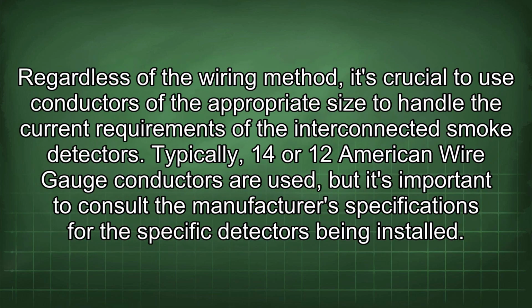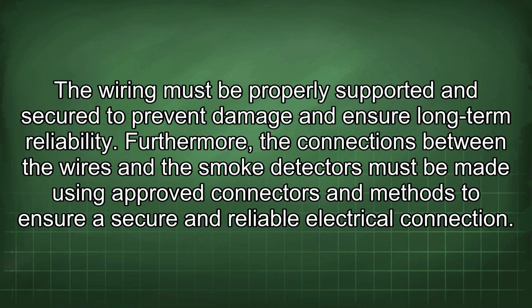Regardless of the wiring method, it's crucial to use conductors of the appropriate size to handle the current requirements of the interconnected smoke detectors. Typically, 14 or 12 American wire gauge conductors are used, but it's important to consult the manufacturer's specifications for the specific detectors being installed. The wiring must be properly supported and secured to prevent damage and ensure long-term reliability. Furthermore, the connections between the wires and the smoke detectors must be made using approved connectors and methods to ensure a secure and reliable electrical connection.